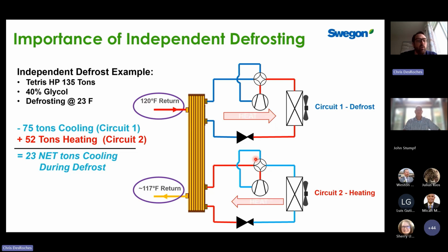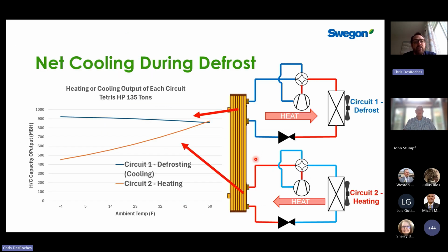So visually, if we look at this on a graph, it might help illustrate. This is looking at what each circuit is outputting as a function of ambient temperature. So you actually see in this chart, it's at 49 Fahrenheit where they balance each other and cancel each other out. As it gets colder, our capacity goes up slightly from the circuit that's in cooling, and the circuit that's in heating, our capacity drops off because we lose capacity as it gets colder.